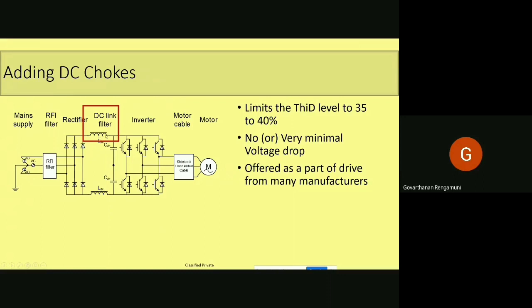Here we see a very nominal voltage drop because we are adding it on the DC side. The major current flowing through this inductor will be DC, and only a minor AC current, the ripple current, will flow. The drop across the inductor is always due to those minor AC currents, because we know very well the drop across an inductor is due to alternating current only. So normally VFD manufacturers offer this as a part of the drive.